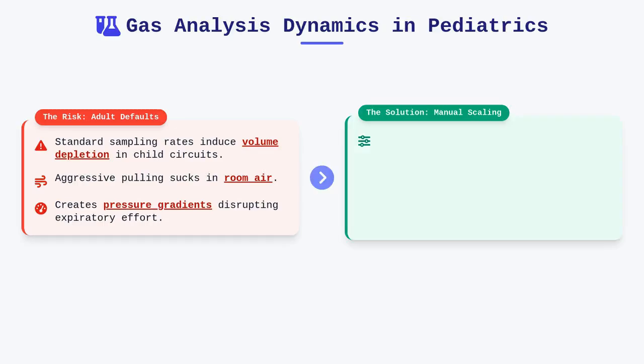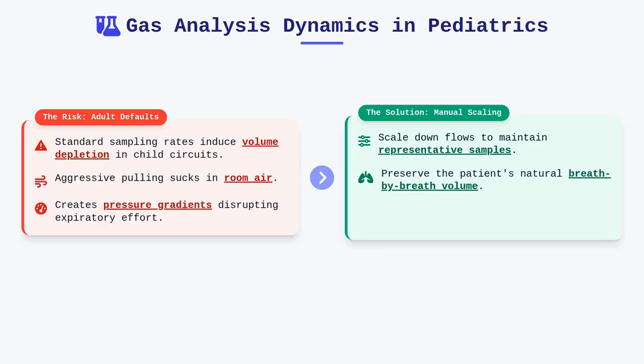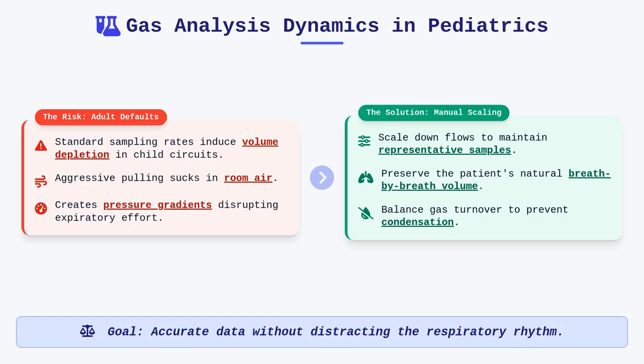We must manually scale down the sampling gas flows to a level that provides a representative sample without physically altering the patient's breath-by-breath volume dynamics. This is a delicate balance of maintaining sufficient gas turnover to prevent water vapor condensation while ensuring the sampling process itself doesn't become a distractor to the patient's respiratory rhythm.